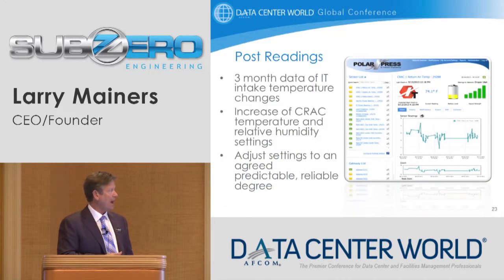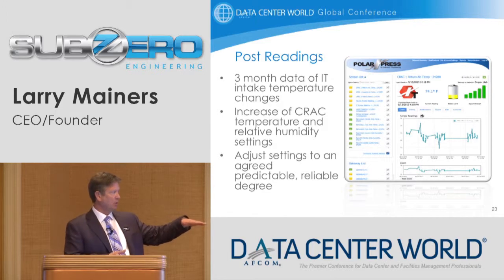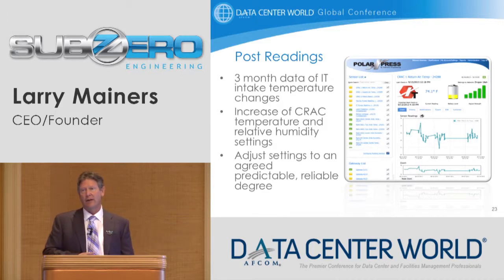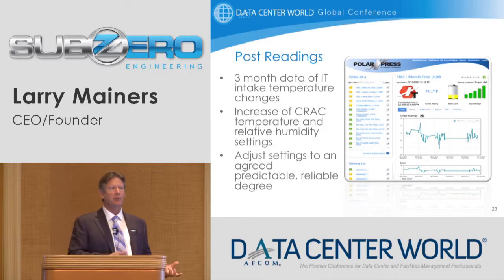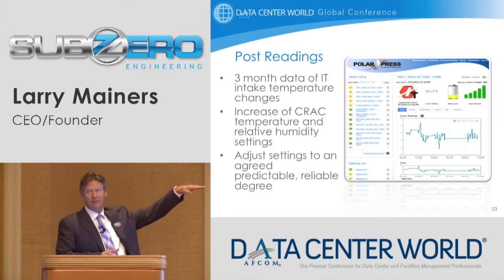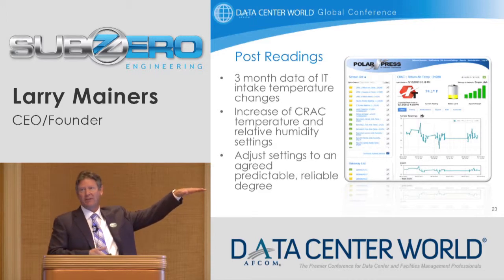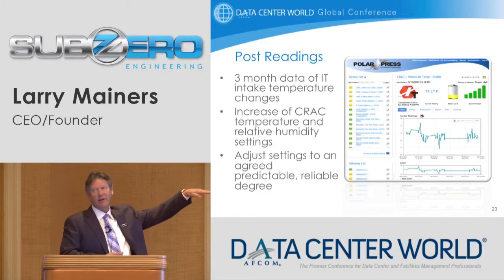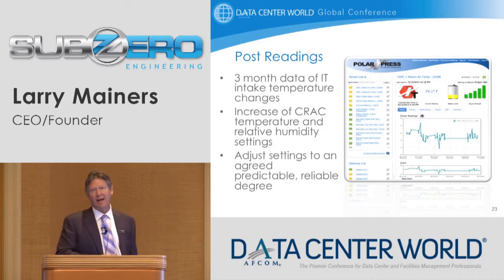You should be able to track it over a period of time, watching the thermal load move in the data center, making certain that whatever changes you make cover the highest load. So if there's a thermal load spike at 2 a.m., say they're dumping something in China or something, we want to make sure our set points can cover whatever thermal load is created by that activity.